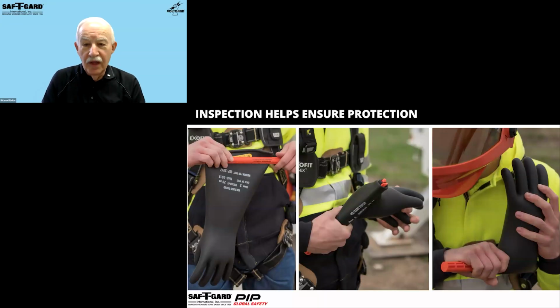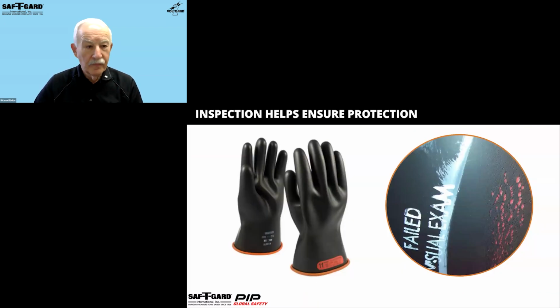Expand the rubber insulating glove to no more than 1.5 times its normal size and look for any damage. The use of two-color rubber insulating gloves, such as the one that I just showed, where the inside is a contrasting color, can aid in the identification of problems, because once it's inflated, you can see through to the inner color, and that's an indication that that glove is no longer safe for use.